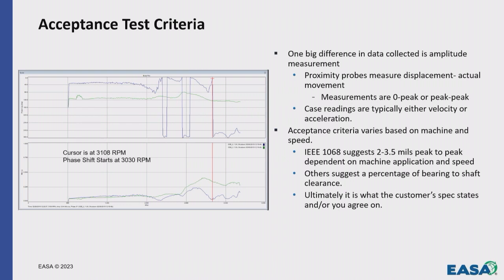The acceptance criteria just varies based on the machine, the class, the customer, and the spec. 1068 suggests 2 to 3.5 mils peak to peak, depending on machine application and speed. You get in some API specs, they're as low as a mil. So it really depends on what you and your customer agree on, but you definitely want to be, when you ship the motor, less than 25% of the gap of the bearing. So if you had a 10 mil bearing, 2.5 mils ought to be the max you're at to ensure it's healthy when it goes out in the field.